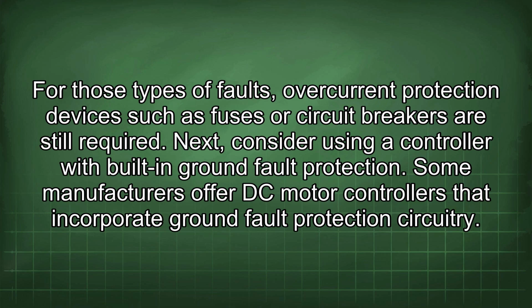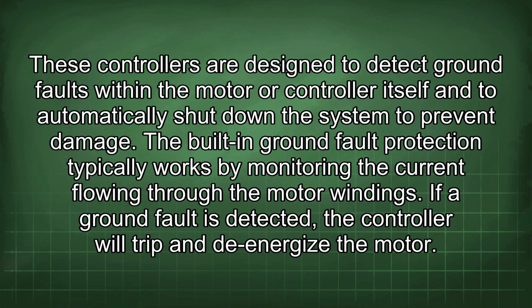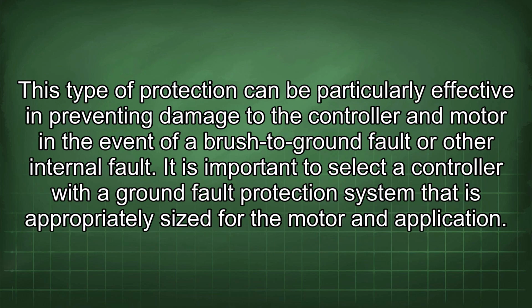Next, consider using a controller with built-in ground fault protection. Some manufacturers offer DC motor controllers that incorporate ground fault protection circuitry. These controllers are designed to detect ground faults within the motor or controller itself and to automatically shut down the system to prevent damage. The built-in ground fault protection typically works by monitoring the current flowing through the motor windings. If a ground fault is detected, the controller will trip and de-energize the motor. This type of protection can be particularly effective in preventing damage to the controller and motor in the event of a brush to ground fault or other internal fault.